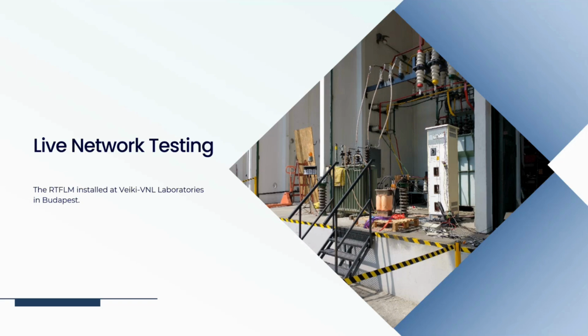So the real-time fault level monitor was just deployed within that live network facility, connected up exactly as it would be on our distribution network, allowed to run to capture fault level measurements, and then they closed the breaker to create that air fault and measured the fault current. Incidentally, this was all during COVID, so we all had to jump through multiple hoops to get people to actually travel there to keep the project on track, which was an interesting time for everyone, I think.